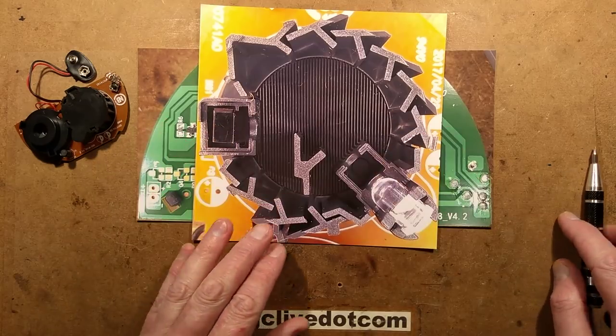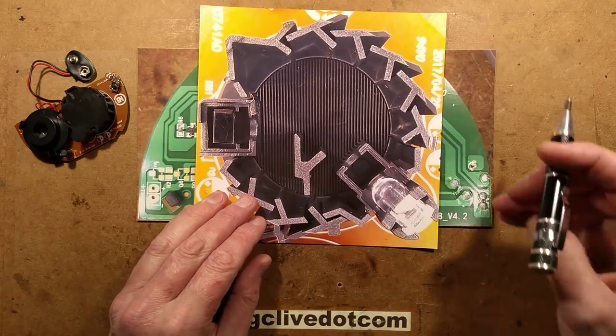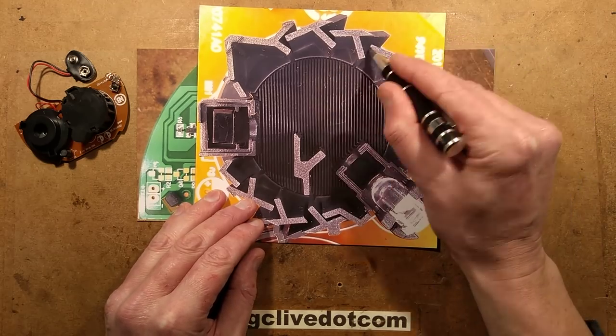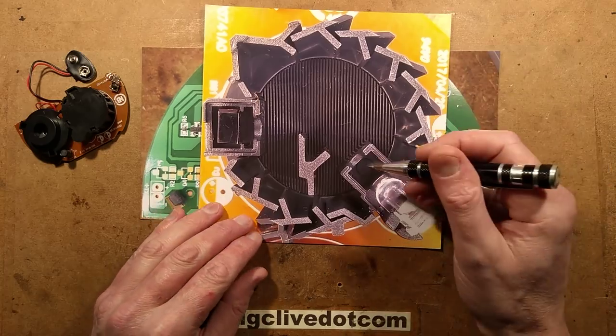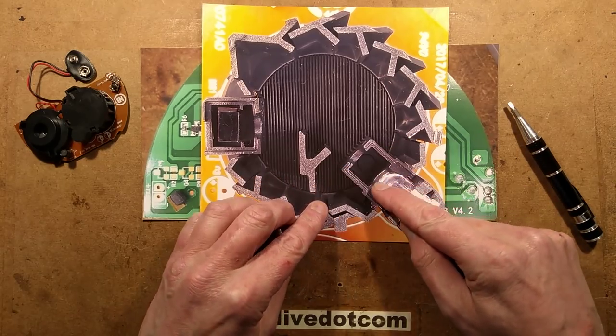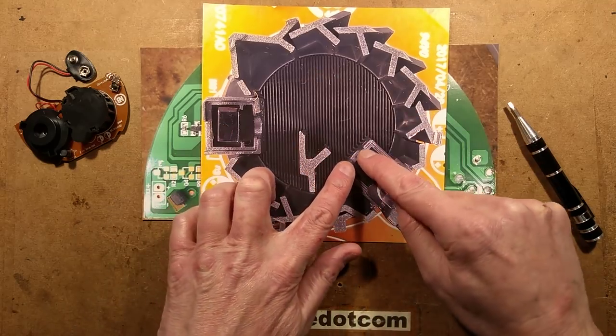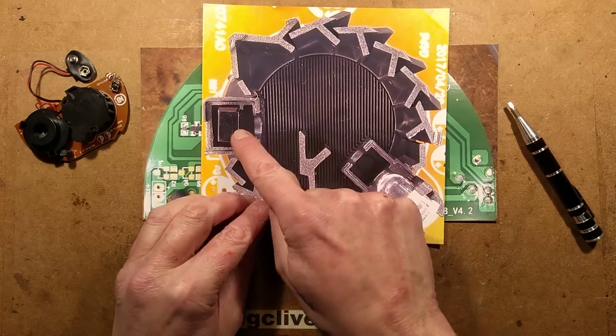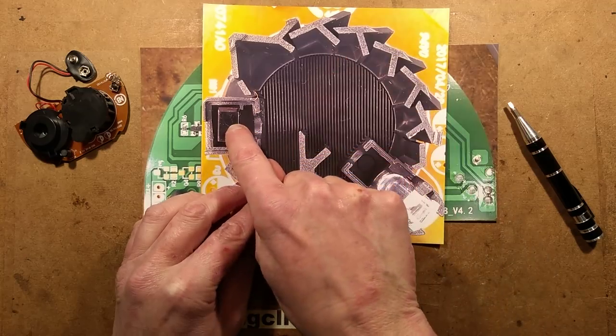Reflecting off the smoke. And it's all ribbed, everything is designed to stop light coming into this or to stop reflections. So if light comes from the outside it can't shine directly. The air can flow through the smoke through these channels, but the light can't come in and it's all jet black and matte to stop reflections working them in. I suppose that under extremely bright conditions it could get in. The emitter here is in a little chamber which deliberately fires it in a cone that misses this completely. And this little barrier here is to stop any reflection, even though this is tapered, it's designed to stop any reflection at all coming from this port here and shining into that. So the only way this can actually see smoke is if it fills the cavity in here and it's being illuminated by the infrared beam and it's seeing the reflection in the sensor. So that's how it works.